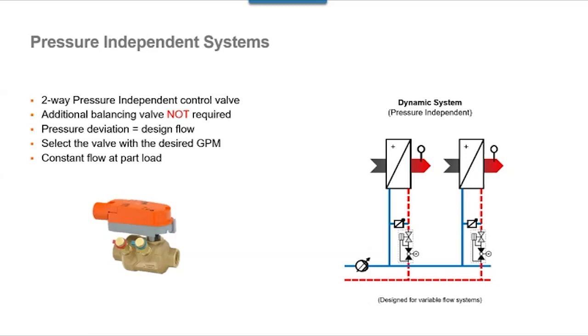Well, I was looking the other day in preparation for this, and I know this was a question I asked Brian before. I said, well, how much pressure drop do you need across a balancing device? I looked at some of the common auto flow devices, and the pressure requirements across them ranged from 1.2 to 7.3 PSI. So I'm going to put in a pressure independent valve that requires 5 pounds. I'm replacing a modulating control valve that requires 4 to 5 pounds, and I'm eliminating that auto flow device that could take anywhere from 1 to 7 pounds. I don't see where the 5-pound pressure independent valve is going to be that much of a hardship on your pump head. The devices you're taking out have some pressure requirements as well.